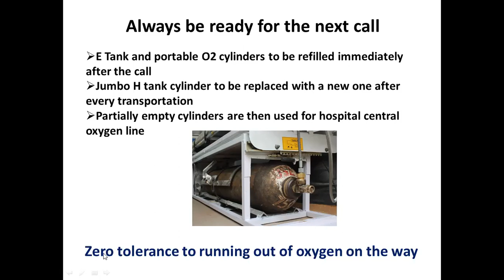We do not say how much oxygen is left, that it was 120 and now it is 100, or 60, it will still last one more call. We don't really do that. Even then we remove the cylinder and put a fresh new cylinder with 120 psi. Partially empty cylinders are then used for the hospital central oxygen line. We do it this way. We have zero tolerance to running out of oxygen on the way.